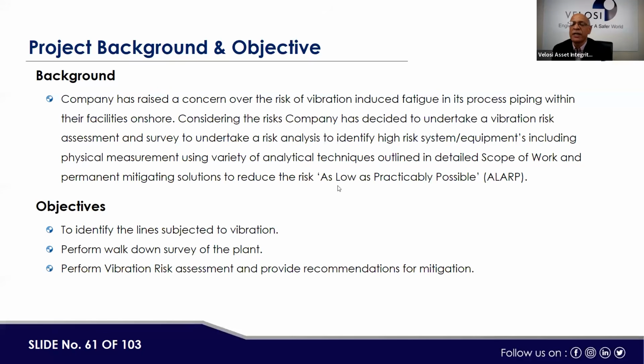As there are typically several causes contributing to the vibration in the piping, as shown in the example, how can we determine the driving causes or the strongest source of vibration in order to troubleshoot the source of the issue?